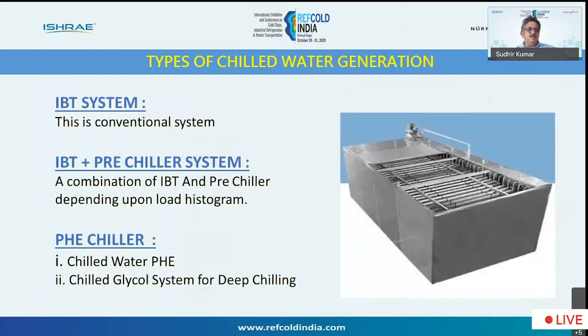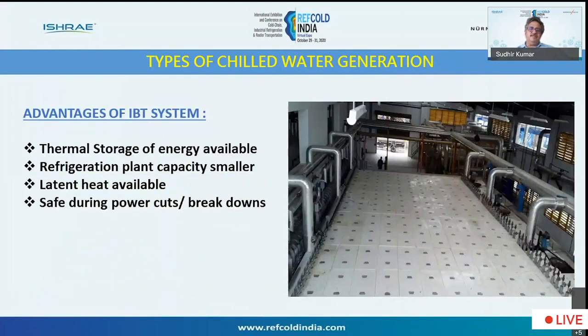And then the next system is, you can use a direct PHE chiller. In some chilling centers, they don't go for IBT system. They only use chilled water PHE system. Or you can use a glycol for deep chilling. If the milk has to go for a longer duration, then you cool it to an even lower temperature using glycol system. The major advantage of an IBT system is the thermal storage is available. Say in some places, if there is a differential power tariff, in the nights the power is less, then this IBT system becomes more relevant. And also the design of the system becomes smaller because you divide the total plant load by 20 hours of operation, and then the refrigeration plant capacity becomes smaller. And similarly, these are safe during power cuts and breakdowns, which I explained to you earlier also.